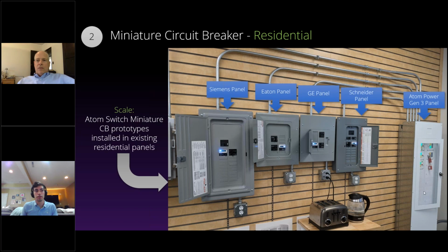Yeah, so this commercial grade panel here can hold 14 breakers inside of it. Depending on how many are on a floor, you could put 14 breakers, so you could feed 14 apartments, I guess, per panel. Gotcha. So if you had something like 50 units, could you put multiple? Yeah, you could have multiple panels. The limit is 14 or 400 amps of the bus bar rating, whichever is your limiting factor. And now with energy management, you might be able to put more on, but it just depends if the residents are okay with you switching on and off their water heater if you get too close to the bus rating.